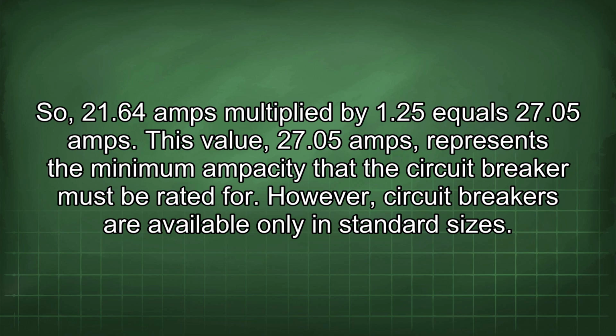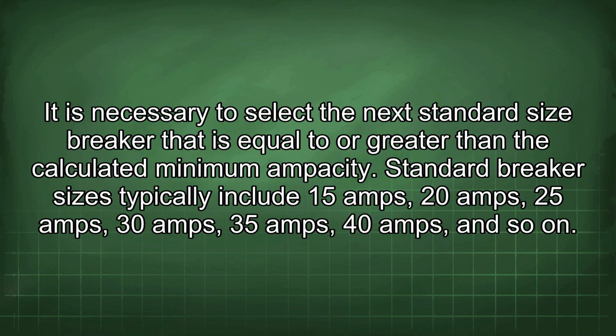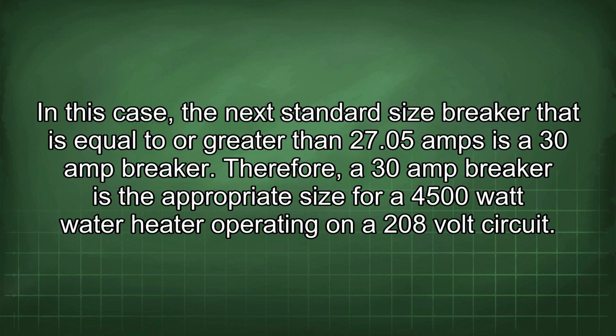However, circuit breakers are available only in standard sizes. It is necessary to select the next standard size breaker that is equal to or greater than the calculated minimum ampacity. Standard breaker sizes typically include 15 amps, 20 amps, 25 amps, 30 amps, 35 amps, 40 amps, and so on. In this case, the next standard size breaker that is equal to or greater than 27.05 amps is a 30 amp breaker. Therefore, a 30 amp breaker is the appropriate size for a 4500 watt water heater operating on a 208 volt circuit.